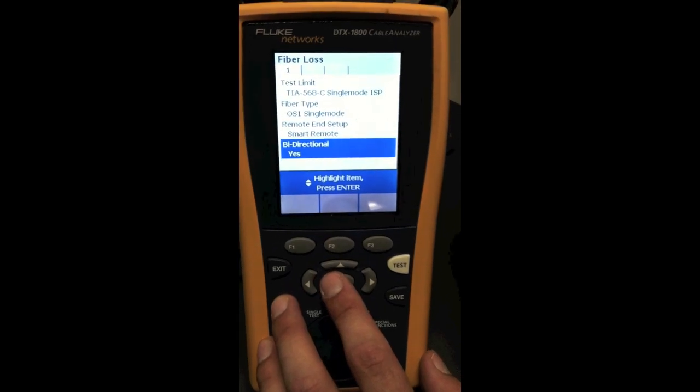If we had our multi-mode adapter and of course right now we want to leave it for OS1. Our remote end setup is always going to be set to a smart remote which is the other end of our testing unit. And our bi-directional test is to test from both ends of the cable so it's running two tests at the same time simultaneously.